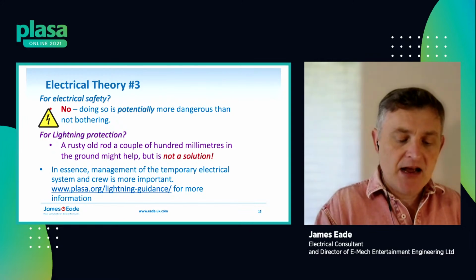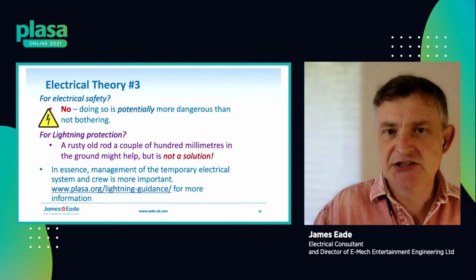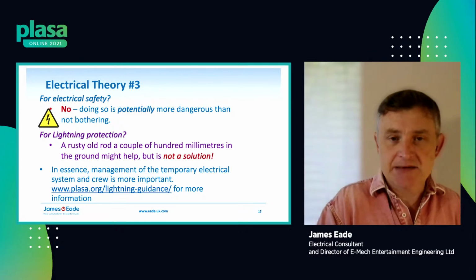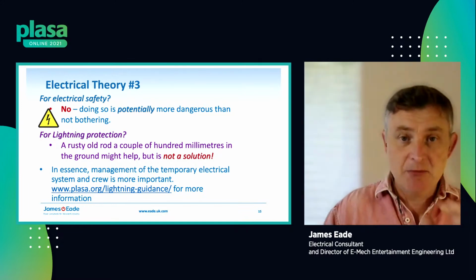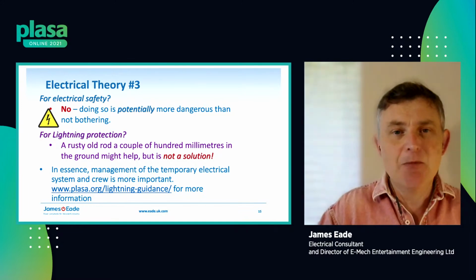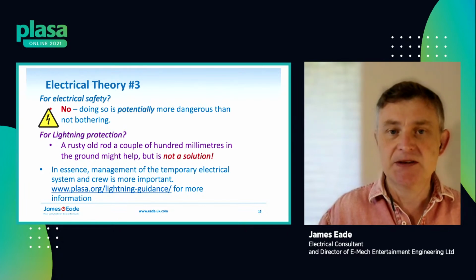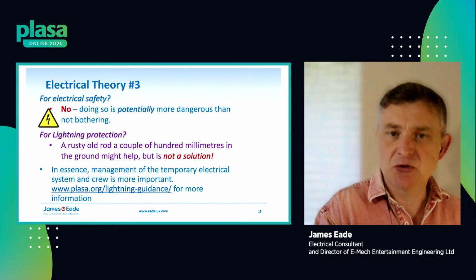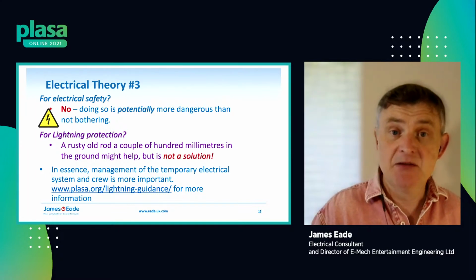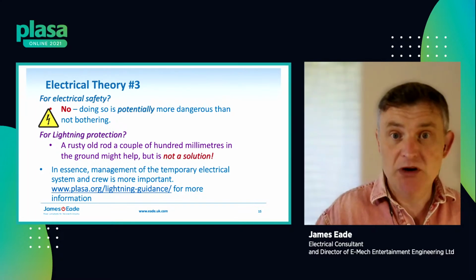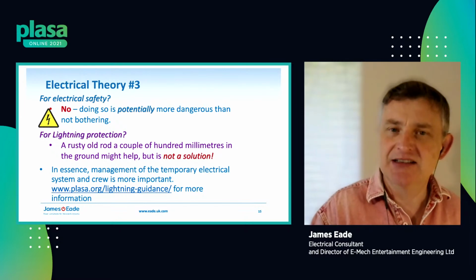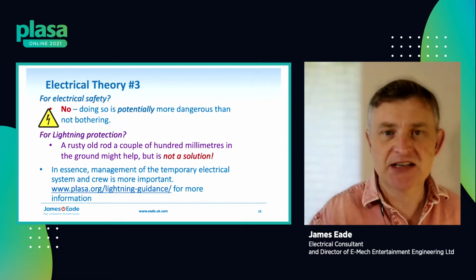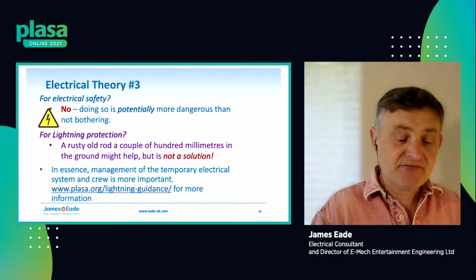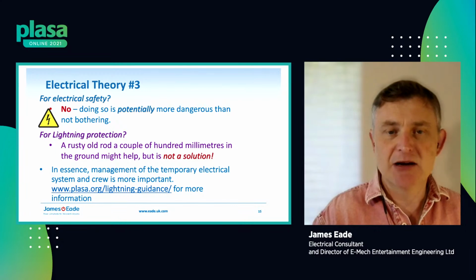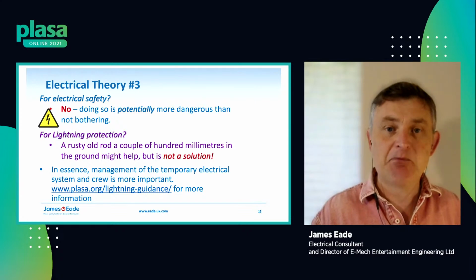The other argument is that it's for lightning protection. A proper lightning protection system needs finials, appropriately sized down conductors, and big earth grids appropriate to the soil conditions. Soil resistivity tests let you work out a good value and how much metalwork needs to be buried. But that's impractical and too expensive for a festival there for a week, for example. Banging a rusty old nail a few hundred mil into the ground might provide a little bit of benefit, but it's by no means a solution.